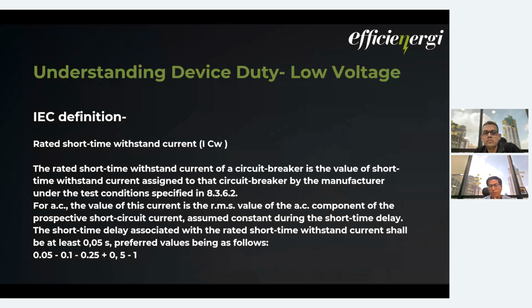Then we have the most important term, which is the rated short time withstand current. This is very important but always overlooked. Again, it is the withstand current assigned to the circuit breaker by the manufacturer, but here you will have a time delay. The short time delay associated with the rated short time withstand current shall be at least 0.05 second, and at maximum you can go up to 1 second, or even in some cases 3 seconds.